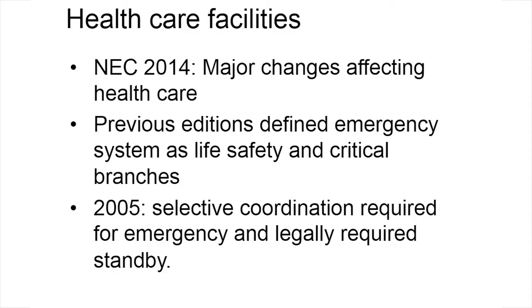Article 517 amended those requirements a little bit, but not much, until 2014. In 2014, the definition of emergency systems disappeared from Article 517. So the prevailing view is that hospitals no longer have a defined emergency system. The three branches, life safety, critical, and equipment, are now considered the essential electrical system with no emergency system defined.